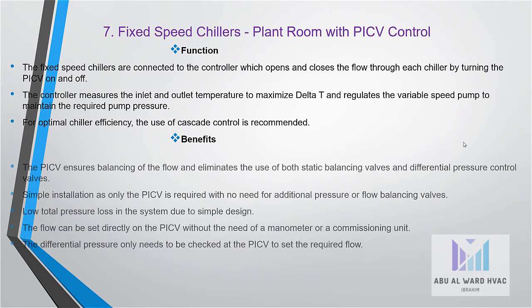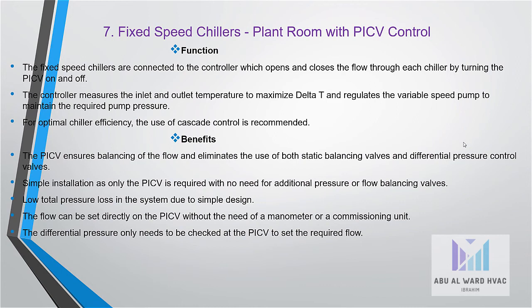The benefits: the PICV ensures balancing of the flow and eliminates the use of both static balancing valves and differential pressure control valves. Simple installation, as only the PICV is required with no need for additional pressure or flow balancing valves. Low total pressure loss in the system due to simple design. The flow can be set directly on the PICV without the need of a manometer or commissioning unit. The differential pressure only needs to be checked at the PICV to set the required flow.